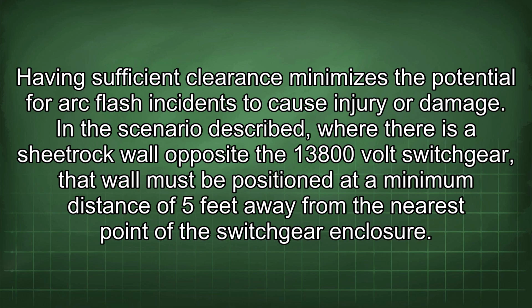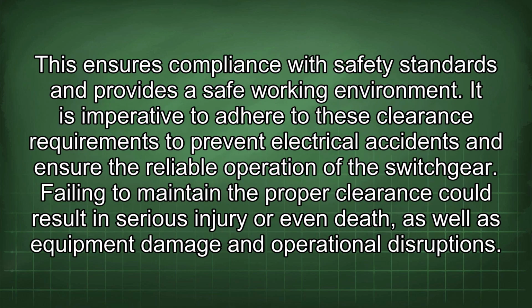In the scenario described, where there is a sheetrock wall opposite the 13,800 volt switchgear, that wall must be positioned at a minimum distance of 5 feet away from the nearest point of the switchgear enclosure. This ensures compliance with safety standards and provides a safe working environment. It is imperative to adhere to these clearance requirements to prevent electrical accidents and ensure the reliable operation of the switchgear.